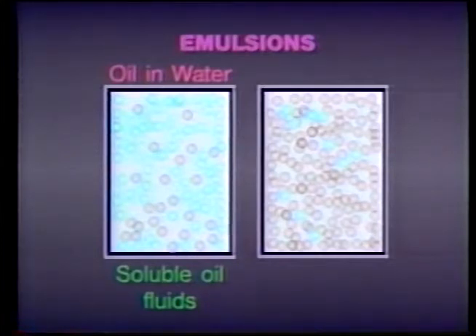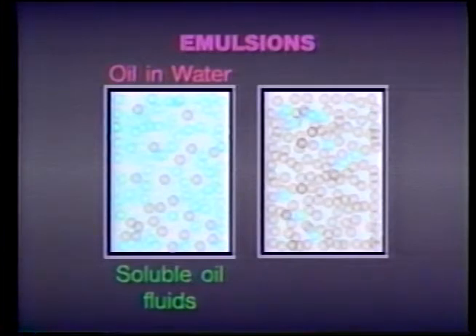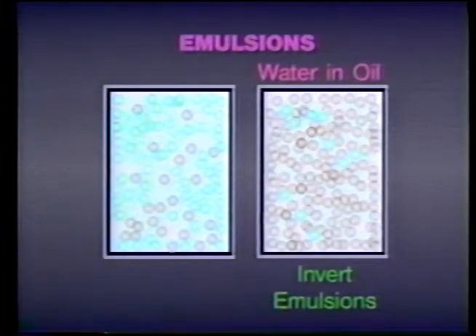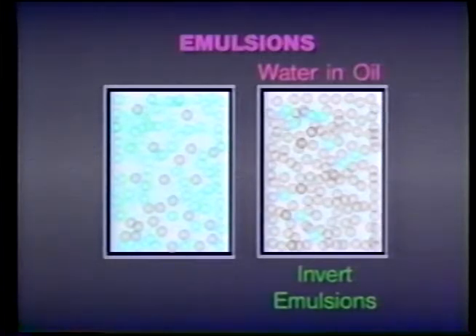However, soluble oil fluids are inexpensive, so you'll still see them used where the decision has been made to accept reduced component life in favor of an inexpensive fire-resistant fluid. When an emulsion has more oil than water, it's called an invert emulsion. They are usually no more than 40 percent water, which means they are less fire-resistant than soluble oils. But because they contain more oil than soluble oil fluids, they provide better lubrication.